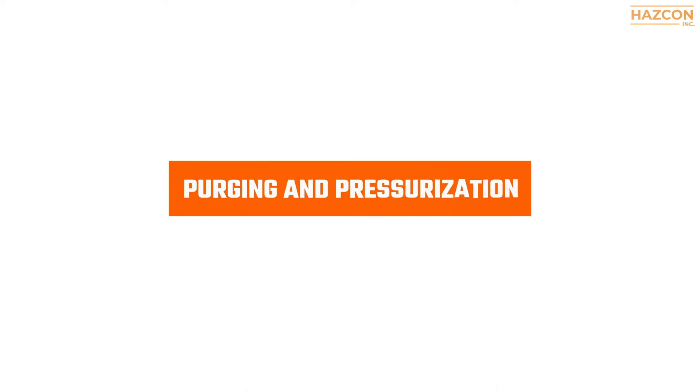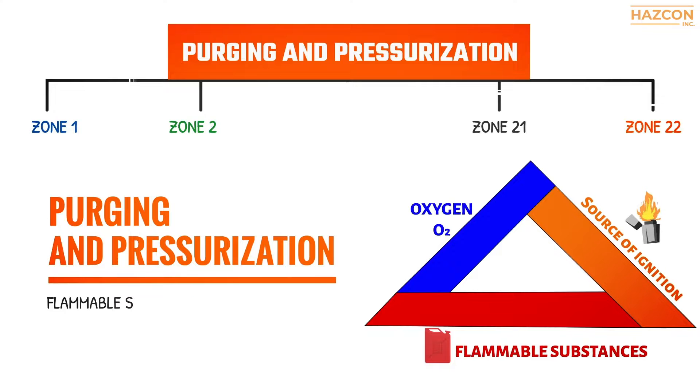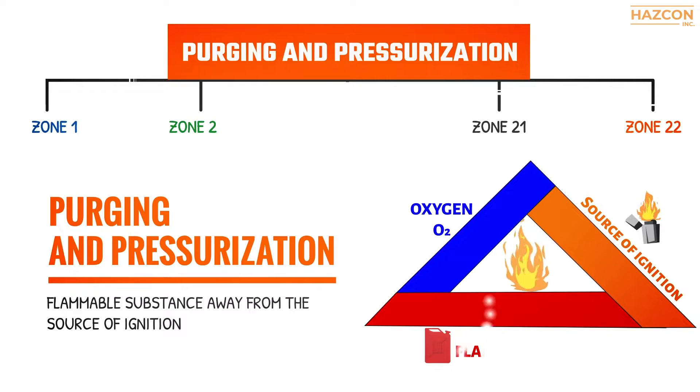The purging and pressurization protection technique, known as EXP, is used for electrical equipment to be installed and used in Zone 1, 2, 21, and 22 hazardous locations. Purging and pressurization involves keeping the flammable substance away from the source of ignition.